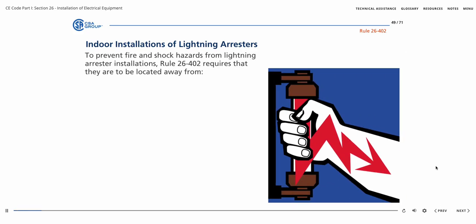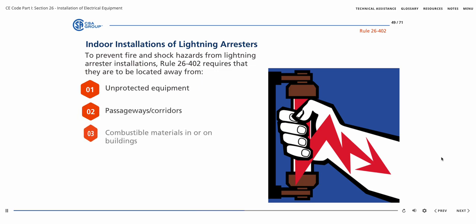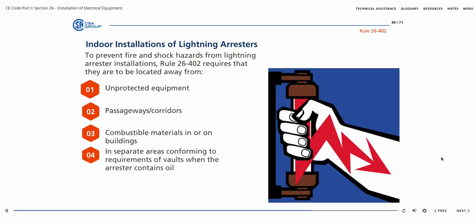To prevent fire and shock hazards from lightning arrester installations, Rule 26-402 requires that they are to be located away from unprotected equipment, passageways and corridors, combustible materials in or on buildings, and in separate areas conforming to requirements of vaults when the arrester contains oil.